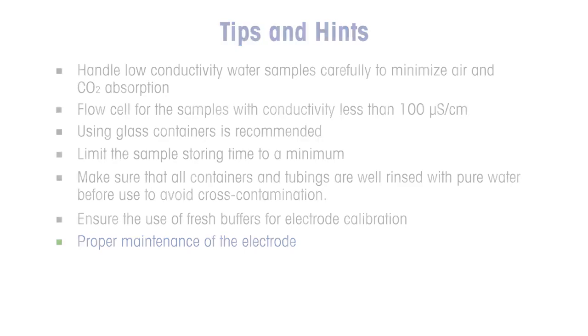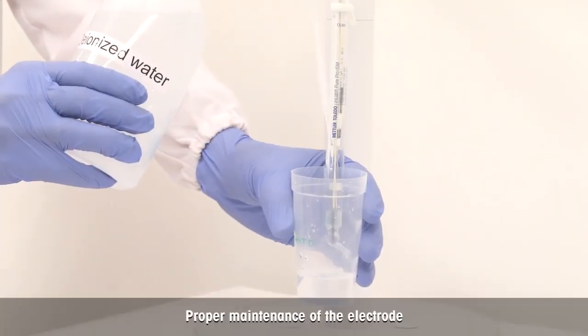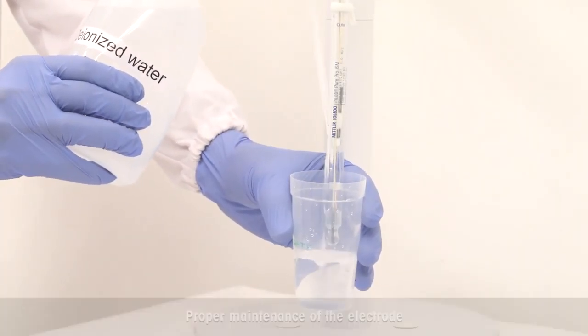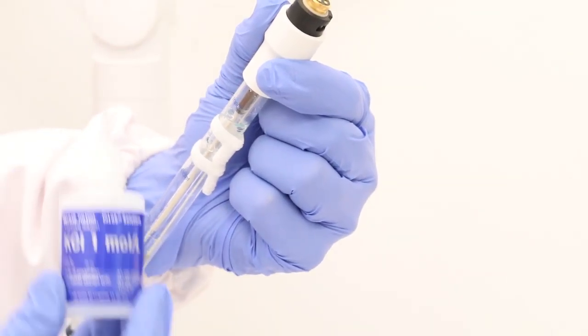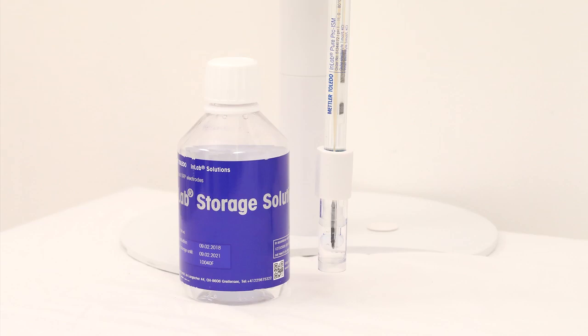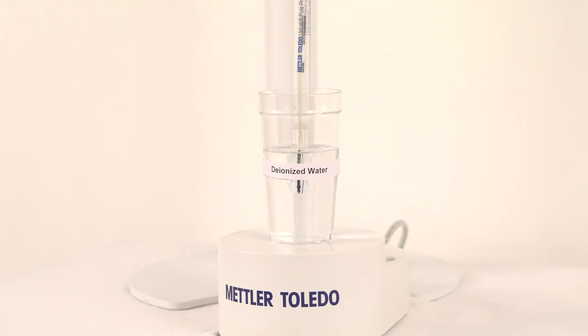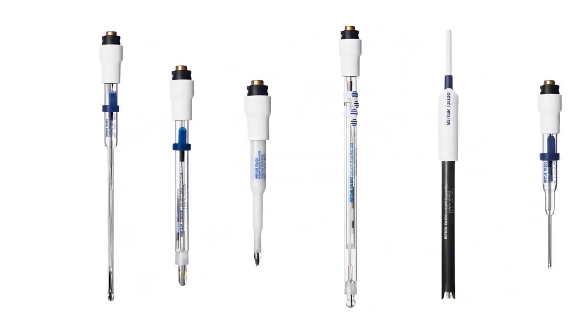Regular maintenance is very important for prolonging the life of the pH electrode. The electrolyte needs to be refilled regularly. Store the electrode in InLab storage solution. Prior to usage, keep it in pure water for 1 minute and rinse it well. Make a proper choice of electrode for your application to achieve better accuracy.